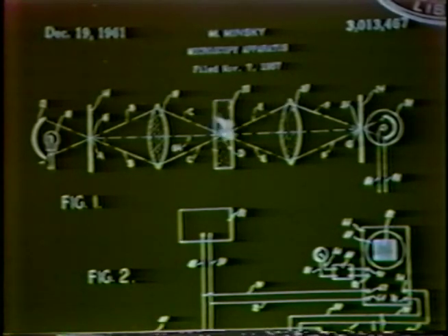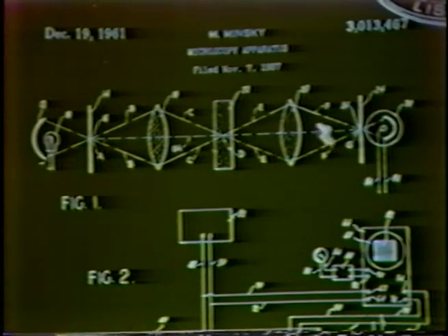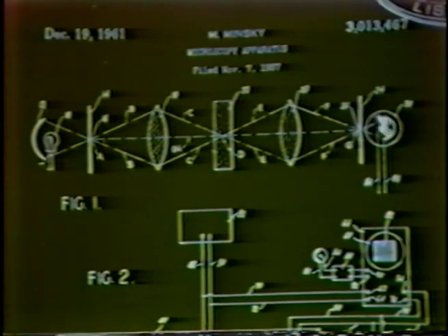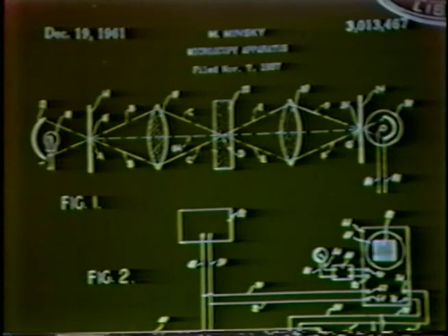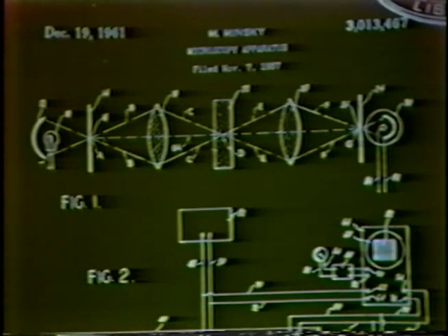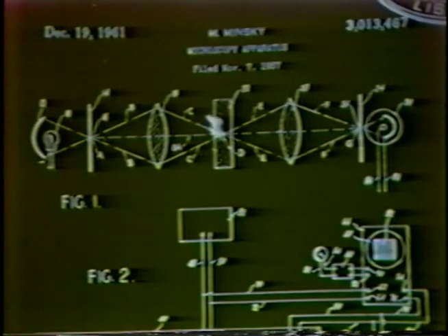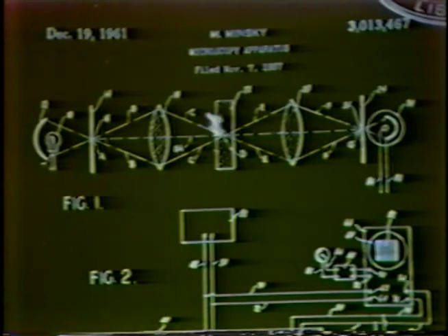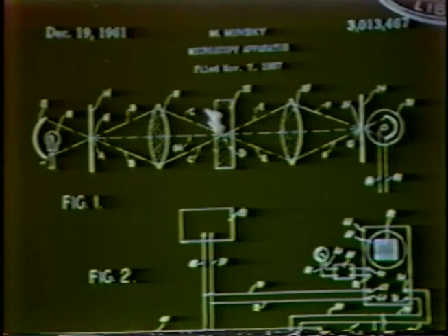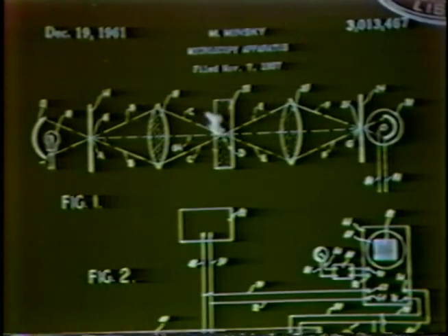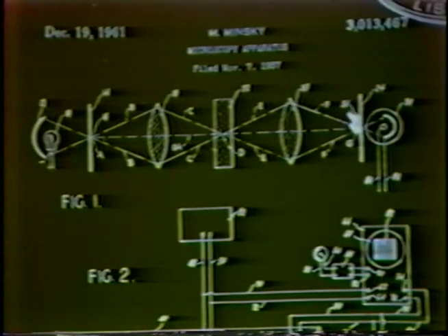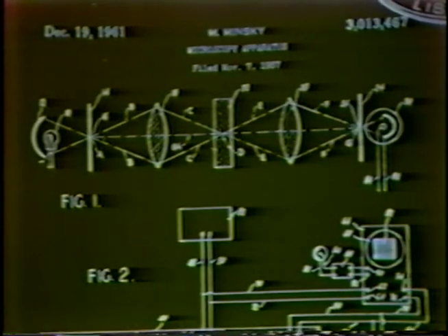And the image of that brightly illuminated point is projected onto an aperture in front of a detector, here shown as a photodiode. And now one can collect information then from that point only, because if the light interacts with the specimen in front of or behind the plane in which we're interested, first of all, it's not very brightly illuminated, and secondly, the point which we're looking at will not be focused properly onto this aperture.